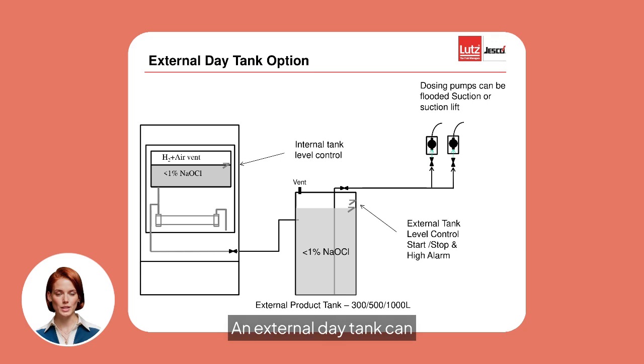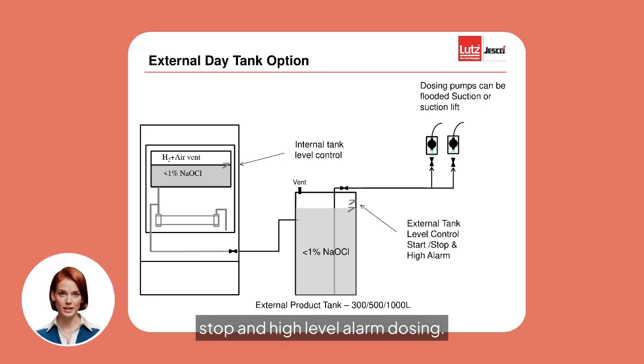An external day tank can be added where larger buffer storage is required. Hypochlorite from the generator fills the external tank, which includes level control for start, stop, and high-level alarm. Dosing pumps can then operate with flooded suction or suction lift, depending on site layout.